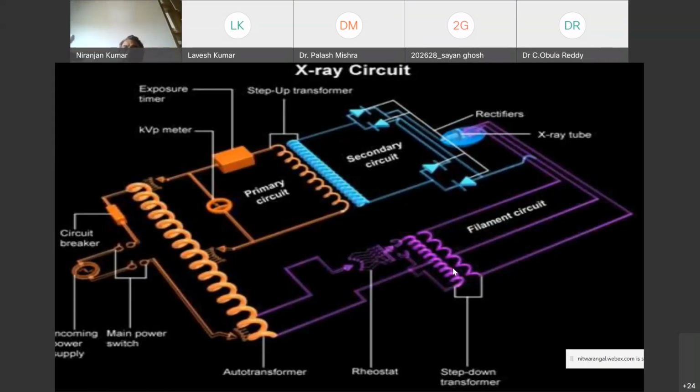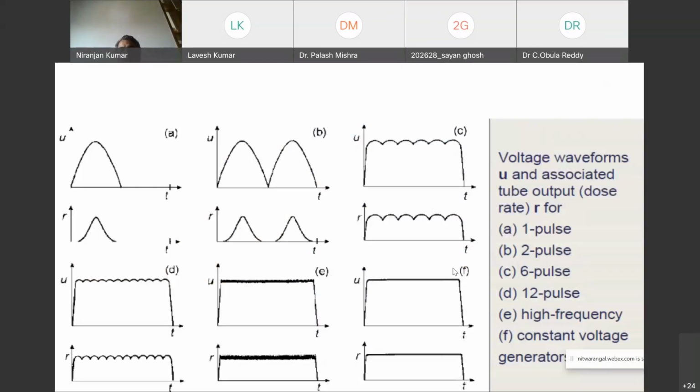And then later everything from the power electronics we started, because this would be very big, you can imagine how big it would be if it is a 150,000 volt transformer. It's like half of the room would be filled with that. Okay, if it is a normal 50 hertz. So that's how the X-ray generator started, and now it is coming into the 10 kHz generator. So a lot of things have happened.